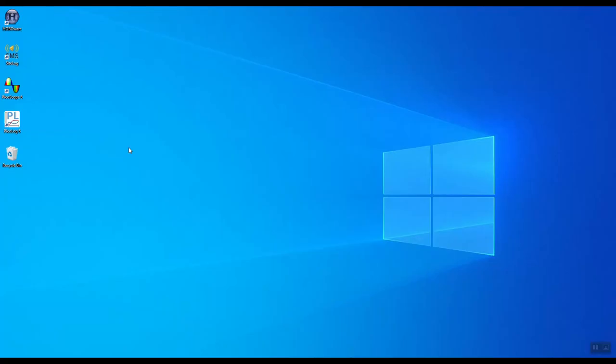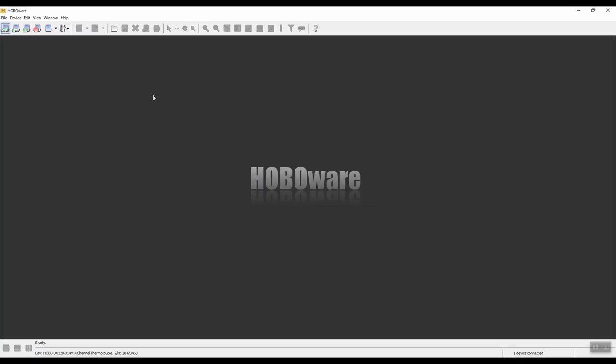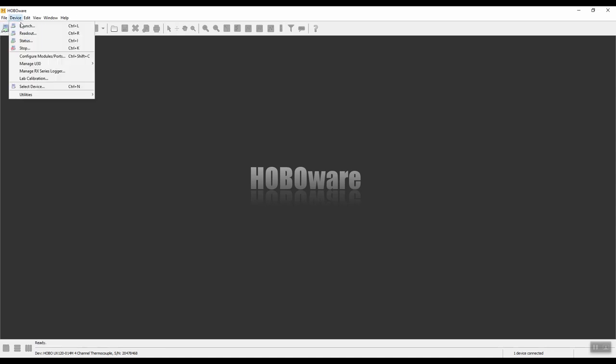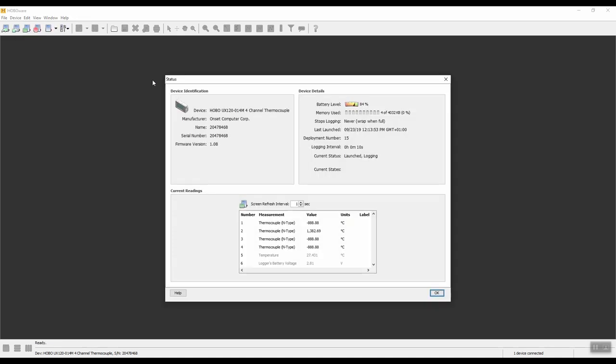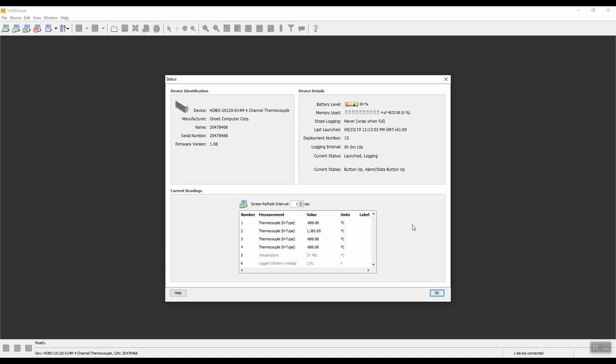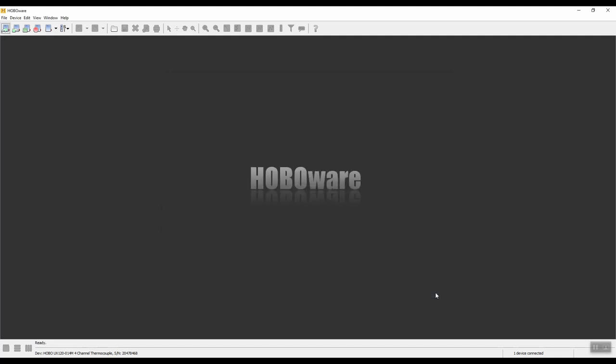I'll show you a few extra features that you may find useful. First, launch the HoboWare software. The first thing we'll do is check what the battery status is and the memory on the device. Go to device and then go to status. Over here you can see what the battery level is and the memory that's actually being used at the moment. What we set it at, at the moment it's wrap when full, when it was launched, logging interval, the channels that are enabled and what types they are, and the screen refresh rate. So if you weren't sure what settings you've had or you wanted to know what the battery level was or how much memory was being used, you can click on this option. Click on OK.